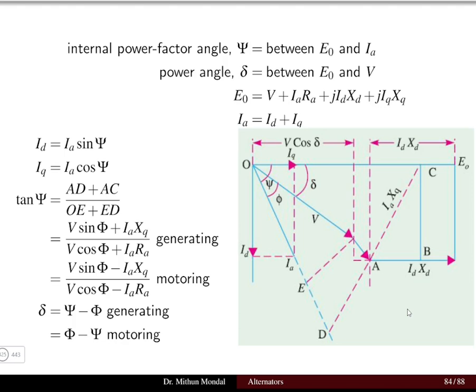To draw the phasor diagram completely and understand the operation of the salient pole machine in both generating mode and motoring mode, we need to know a few terms. The first term is the internal power factor angle, denoted by ψ, which is the angle between the induced EMF E0 and the armature current Ia. The power angle δ is the angle between the induced EMF E0 and the terminal voltage V.